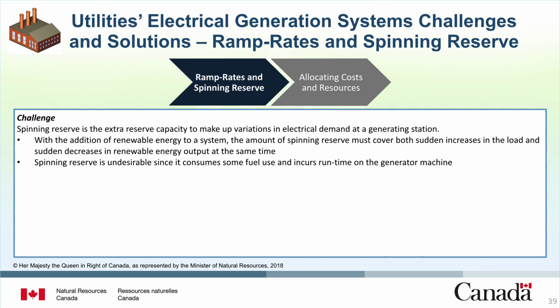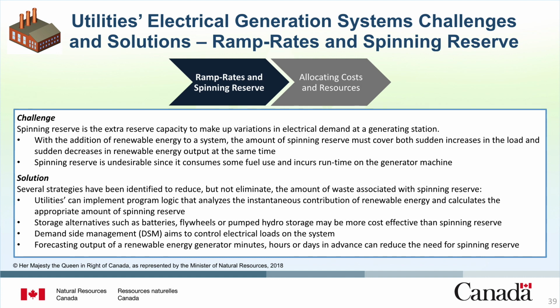Spinning reserve is undesirable since it consumes some fuel and incurs runtime on the generator machine. Much maintenance is planned based on run hours rather than power output. Several strategies have been identified to reduce, but not eliminate, the amount of waste associated with spinning reserve. Utility controls may implement sophisticated program logic that analyzes the instantaneous contribution of renewable energy and calculates the appropriate amount of spinning reserve. Storage alternatives to spinning reserve, such as batteries, flywheels, or pumped hydro storage, may be more cost-effective. Demand-side management, or DSM, is another alternative to spinning reserve, which controls the electrical loads on the system rather than aiming to meet all loads at any given time. Forecasting the output of a renewable energy generator minutes, hours, or days in advance also can reduce the need for spinning reserve. Technical developments in forecasting software have allowed operators of utility transmission and distribution systems to predict in advance solar system or wind output.